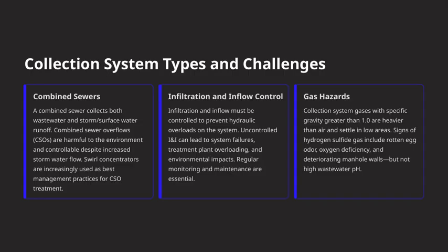Finally, let's discuss gas hazards within collection systems. Gases with a specific gravity greater than 1, like hydrogen sulfide, tend to settle in low-lying areas because they are heavier than air. You can often tell there's hydrogen sulfide present by its distinctive rotten egg smell, and it can cause oxygen deficiency and even deterioration of manhole walls. Interestingly, these hazards are not indicated by high wastewater pH, so awareness and proper safety measures are essential to protect workers and the environment alike.